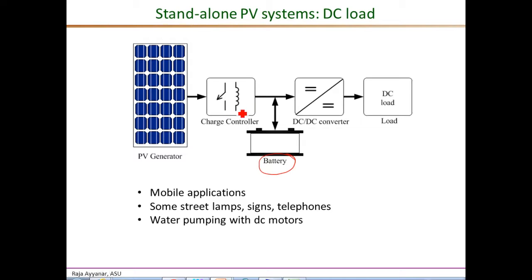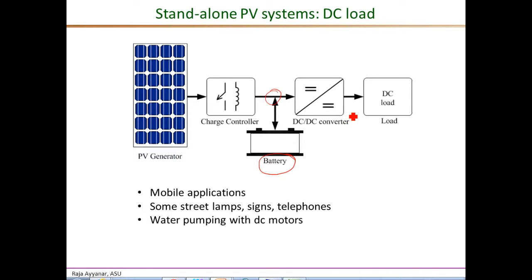We have a charge controller which charges the battery from the PV panels, and we also need a DC-DC converter that regulates the slightly varying battery voltage into a precisely regulated DC voltage as required by the loads. It is also possible to have multiple DC outputs to support multiple DC loads requiring different voltage levels.